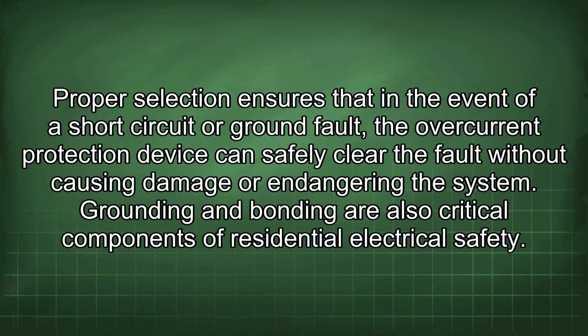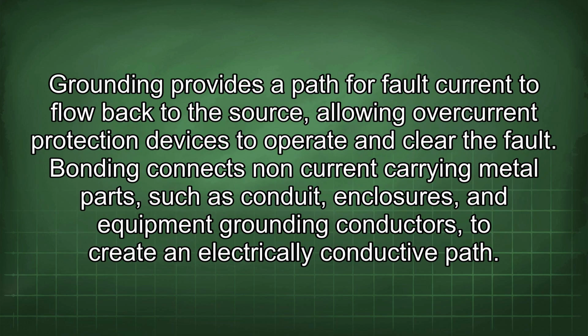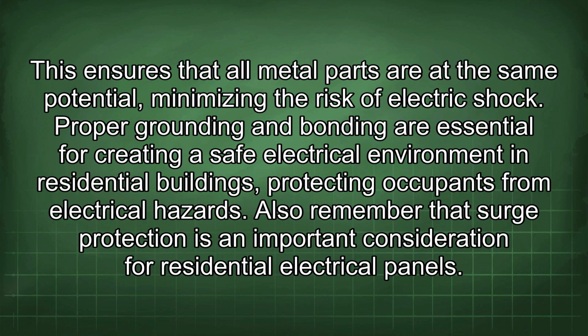Grounding and bonding are also critical components of residential electrical safety. Grounding provides a path for fault current to flow back to the source, allowing overcurrent protection devices to operate and clear the fault. Bonding connects non-current carrying metal parts such as conduit, enclosures, and equipment grounding conductors to create an electrically conductive path. This ensures that all metal parts are at the same potential, minimizing the risk of electric shock. Proper grounding and bonding are essential for creating a safe electrical environment in residential buildings, protecting occupants from electrical hazards.